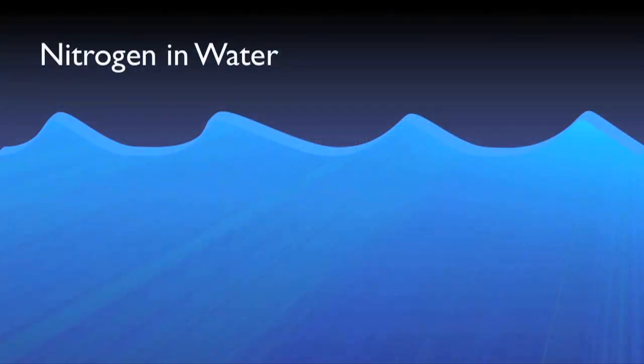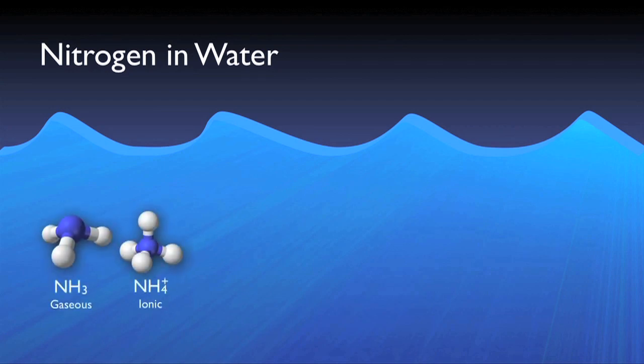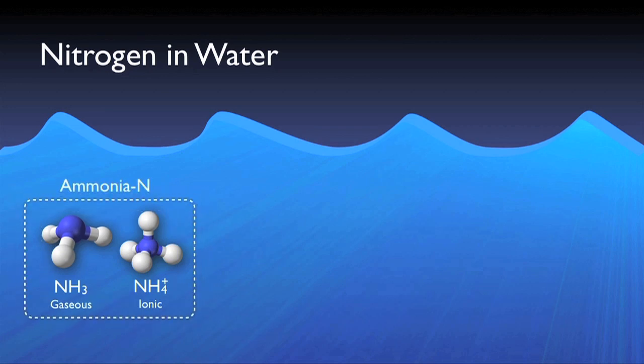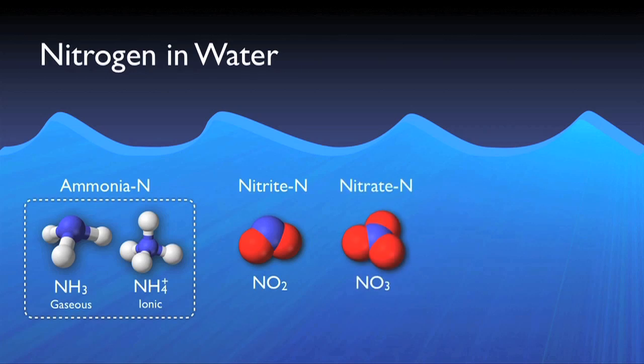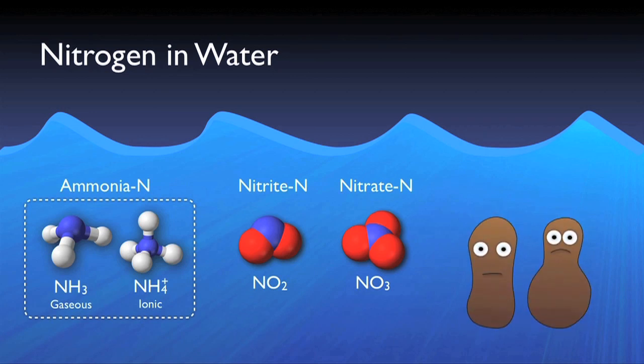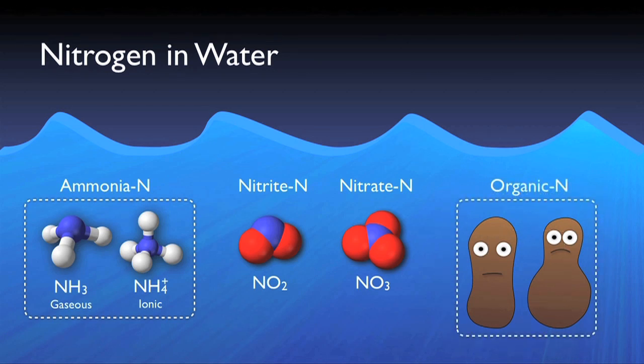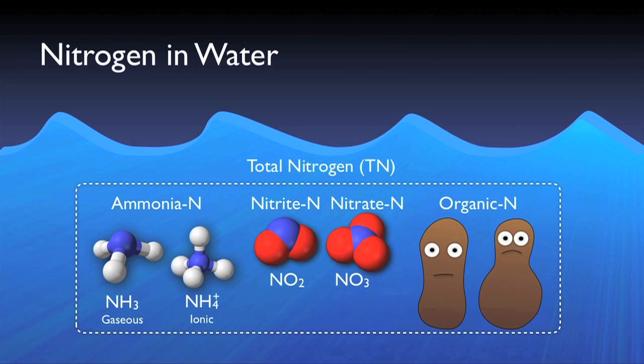Nitrogen is present in wastewater in various forms which have been lumped into separate general categories. Nitrogen in the form of ammonia is ammonia nitrogen. There is also nitrite nitrogen and nitrate nitrogen, which are usually formed during the actual biological processes at the wastewater treatment plant. In addition, nitrogen makes up a small percentage of cell mass of organisms in the system as well as other dissolved organic compounds. This category is referred to as organic nitrogen, of which a certain amount typically cannot be removed through the biological processes described in this video. Total nitrogen, as the name implies, is the sum of all types of nitrogen.